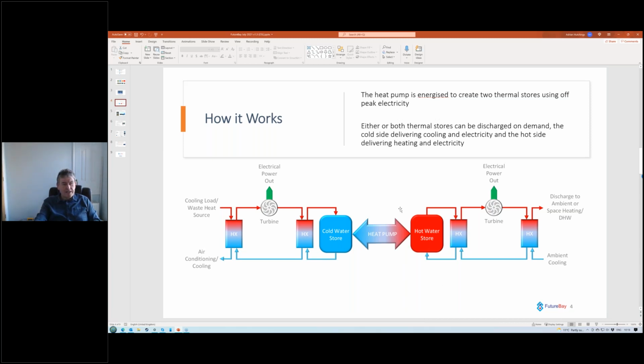At the center is a standard industrial heat pump. For our first demonstrator, we used a heat pump normally used to produce ice for ice rinks. This system is energized when you have renewable, off-peak, or low-cost clean electricity, and as with any heat pump it moves heat from one side to the other, producing a tank of hot water and a tank of cold water. The cold side isn't as cold as your freezer, and the hot side isn't as hot as your kettle, so there are no extremes of temperature or pressure, and no exotic materials.